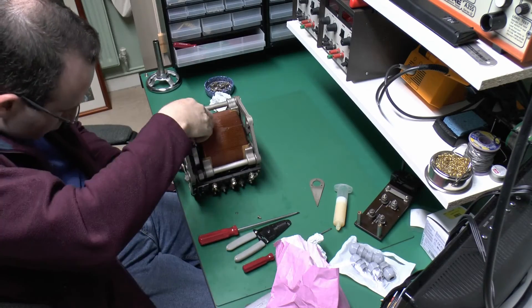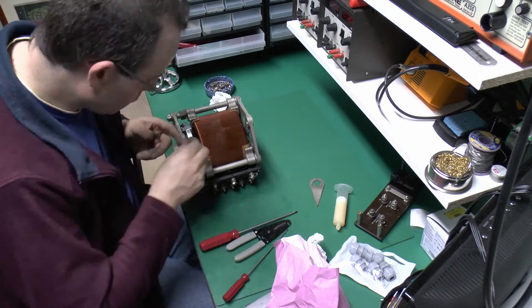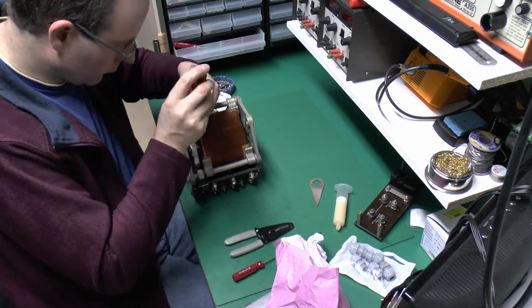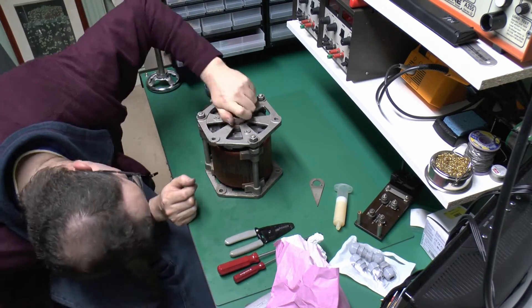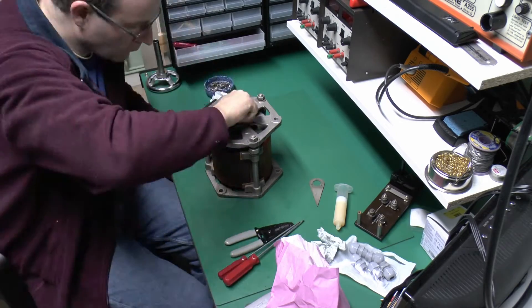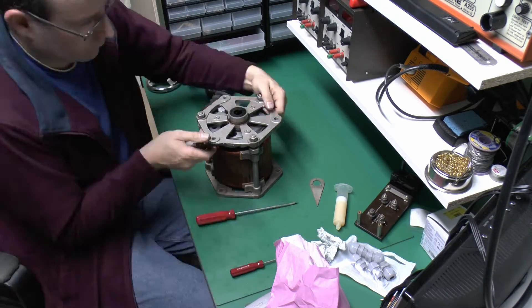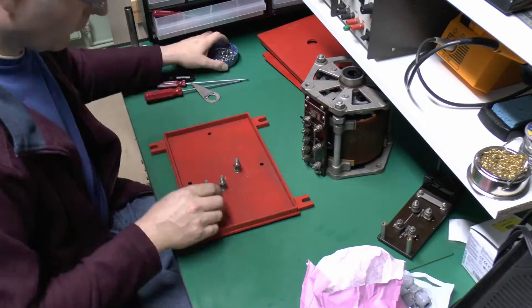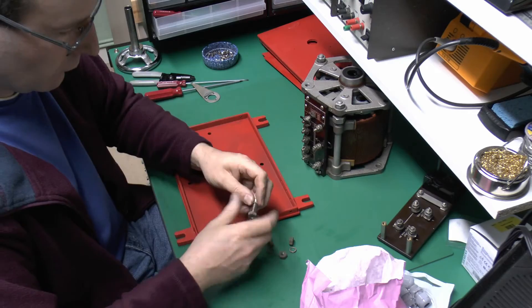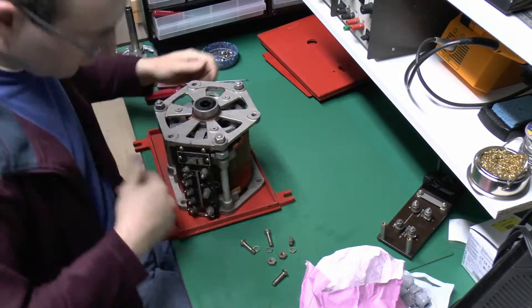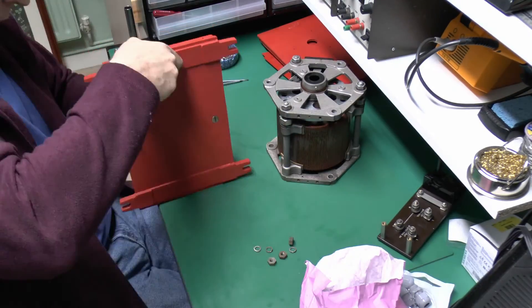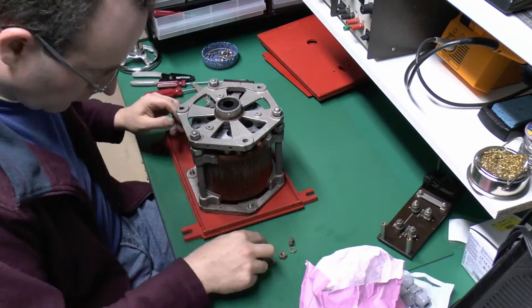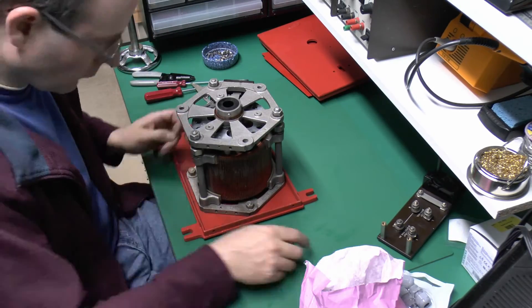And I've just got to alter one of the wires here, this little braided wire which has to go under the spring rather than over it otherwise it tends to bind on the arm that comes across for the contact. So just have to alter that there. Now here we've got the base which has been repainted in that red colour. Just trying that out for the correct fit. Those three bolts go in the bottom and then the whole thing just bolts onto the rather substantial base plate.